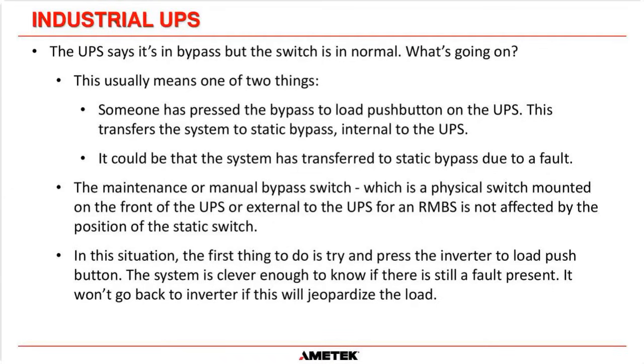The maintenance or manual bypass switch, which is the physical switch, is not affected by the position of the static switch. They can be two completely different positions. So if the manual bypass switch is in the normal position, then the static switch can be in the bypass position. The two are not related. In this situation, the first thing that you should always try and do is press the inverter to load push button. Our system is clever enough to know if there is still a fault present, so it won't go back to inverter if it thinks it will jeopardize the load circuit. So if you walk up to a system and the maintenance bypass switch is in the normal position, but the static switch says it's in bypass, try and press the inverter to load button and see if it goes back to inverter.